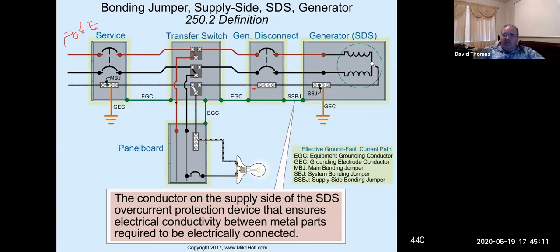Right now, the transfer switch is set to power up my building from the utility. See how the little switches down here, I can actually see the red wire, I can follow it back, and it's switched over from the PG&E side. But if we did need to switch it over to the generator, the transfer switch just automatically flips over to the other side and now routes the power from the generator down to the panel board, right? So that's how a generator works. I know some of you have not seen some of this stuff, but this is a very typical installation that we work on where we have transfer switches. And you may have worked on, I know there's a lot, especially up in the hills, a lot of customers want to have a generator backup system. So this is typically how they look.